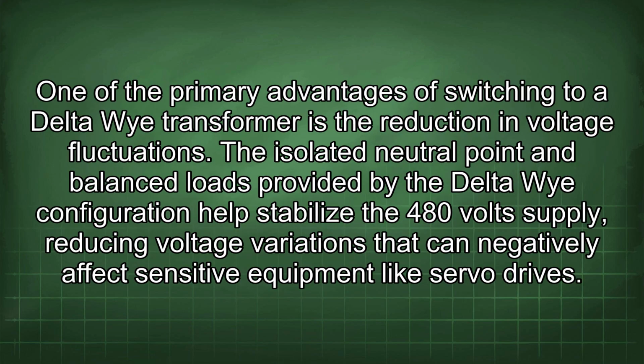One of the primary advantages of switching to a delta-Y transformer is the reduction in voltage fluctuations. The isolated neutral point and balanced loads provided by the Delta Wye configuration help stabilize the 480 volts supply, reducing voltage variations that can negatively affect sensitive equipment like servo drives.